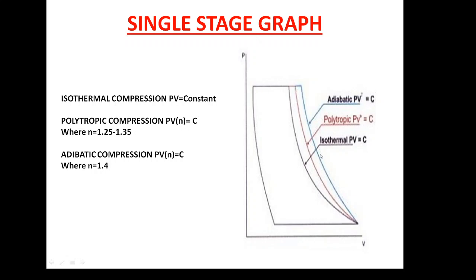There is a constraint that in single-stage compression, maximum pressure can only rise in one go from 1 bar to 30 bar, because after 30 bar there is a material constraint — because of failure of material, metallurgy-wise it is physically becoming impossible due to buildup of heat, lubrication problems, and several other issues which we will discuss when we cover multi-stage.